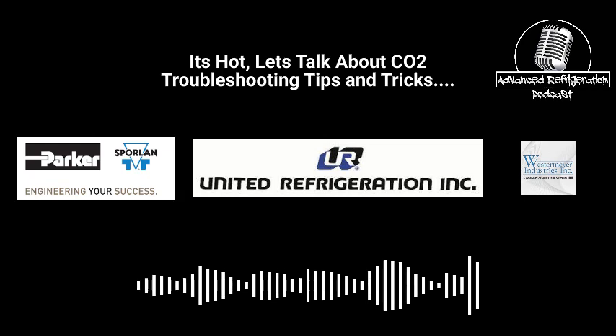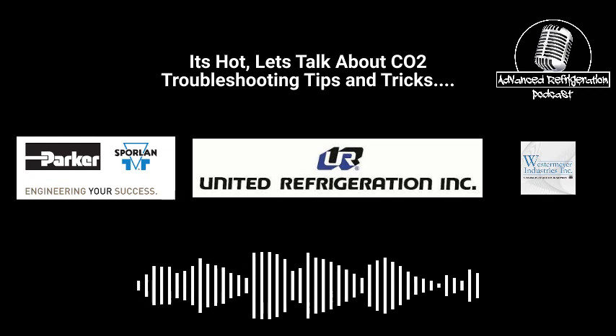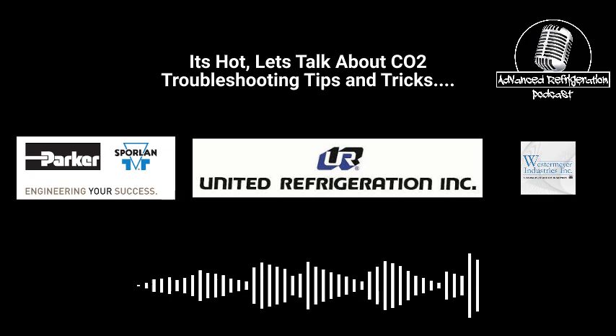Why? There's a theory behind that. Because you have less room for failure if something were to go wrong between the liquid level in the receiver and the flash gas bypass valve. Oh shit. Now I get it. You'd have to have a pipe that's 3 feet off the top of the flash tank to make sure you don't get that liquid. I see what you're saying now. You're still picking it up because it's a wet vapor.